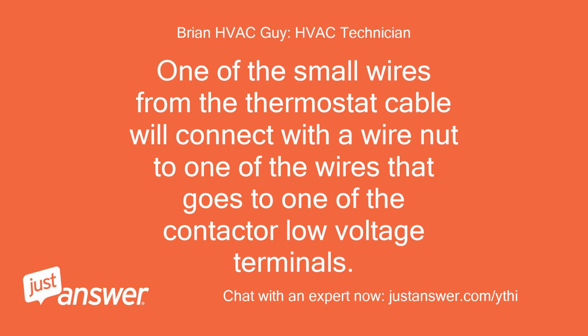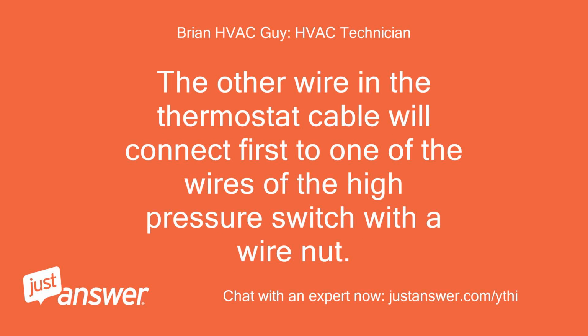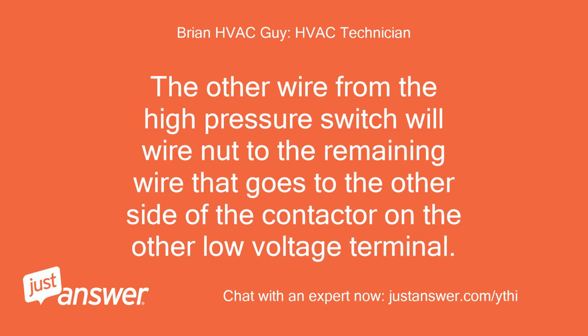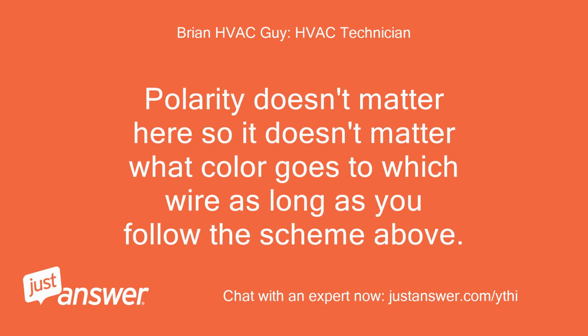One of the small wires from the thermostat cable will connect with a wire nut to one of the wires that goes to one of the contactor low voltage terminals. The other wire in the thermostat cable will connect first to one of the wires of the high pressure switch with a wire nut. The other wire from the high pressure switch will wire nut to the remaining wire that goes to the other side of the contactor on the other low voltage terminal. Polarity doesn't matter here, so it doesn't matter what color goes to which wire as long as you follow the scheme above.